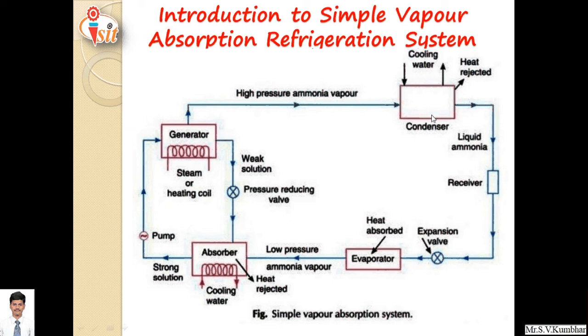This high pressure, high temperature ammonia vapor is sent to the condenser, where it is condensed with the help of a cooling medium — water is shown here. Heat is rejected from high pressure ammonia vapor and it is converted into high pressure ammonia liquid. This liquid is temporarily stored in a receiver, then passed through the expansion valve where pressure reduces considerably, and low pressure, low temperature liquid refrigerant finally flows through the evaporator where heat energy is absorbed from the object to be cooled.